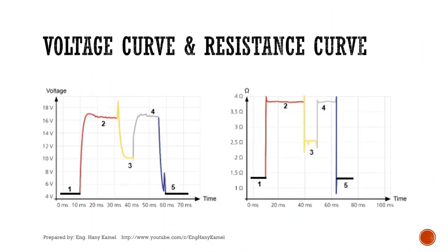For the voltage curve and resistance curve, the sequence is the same as discussed for the current curve. For the voltage curve, it will show the measured voltage drop, and for the resistance curve, it will be calculated from the measured voltage drop and injected current.